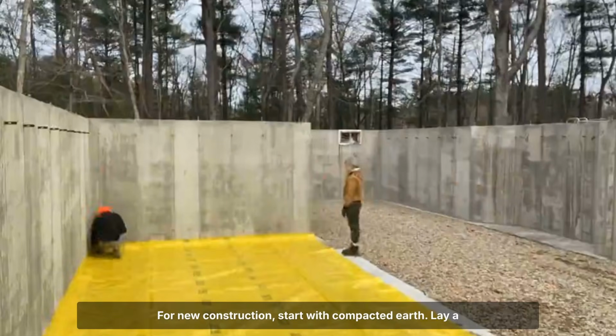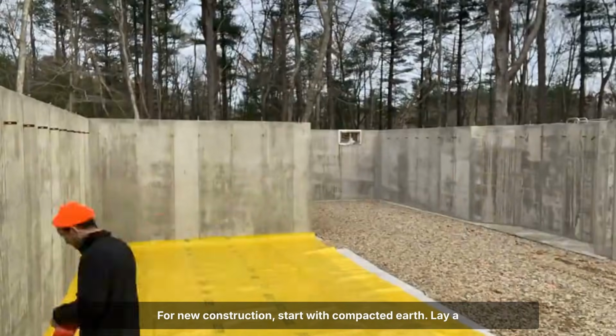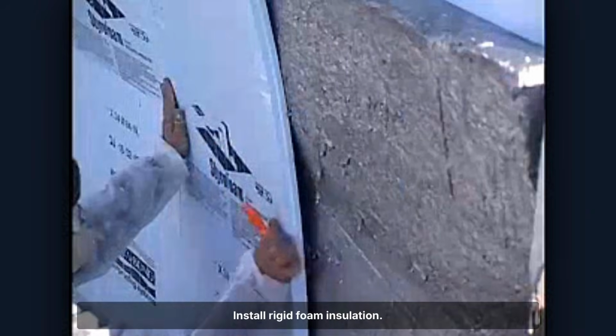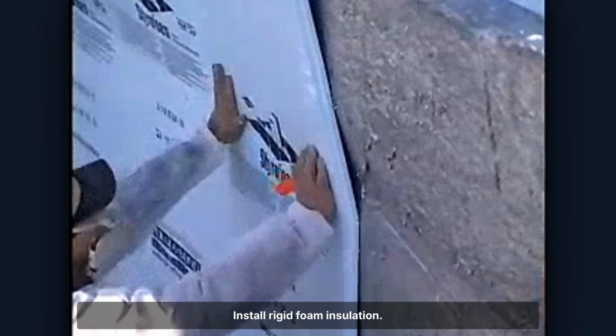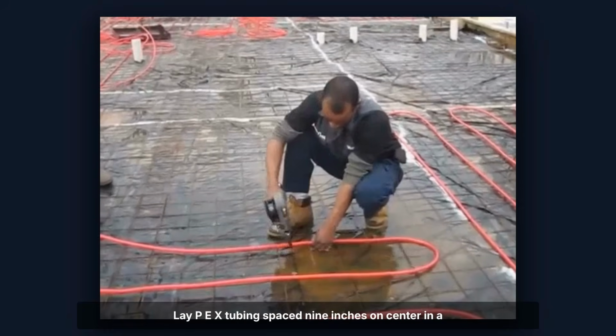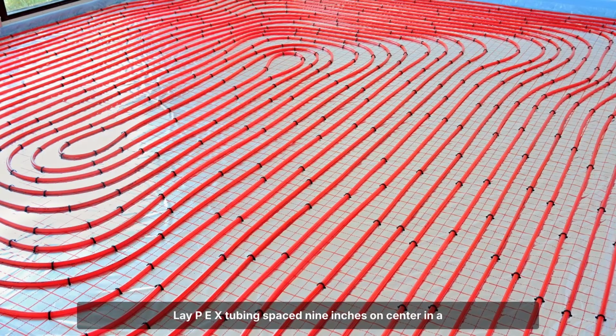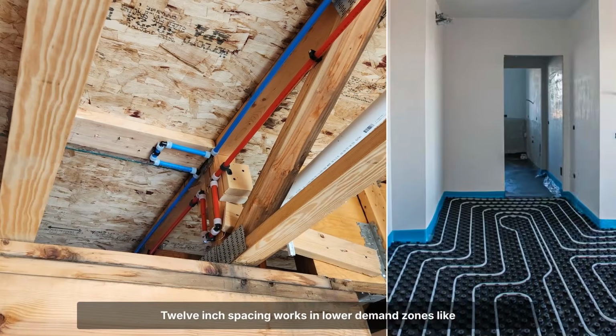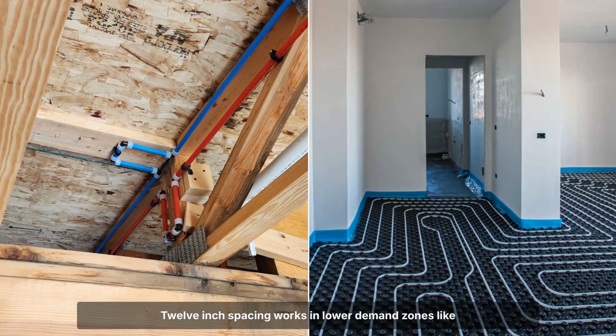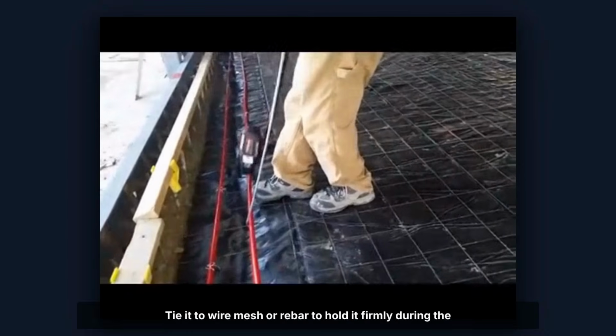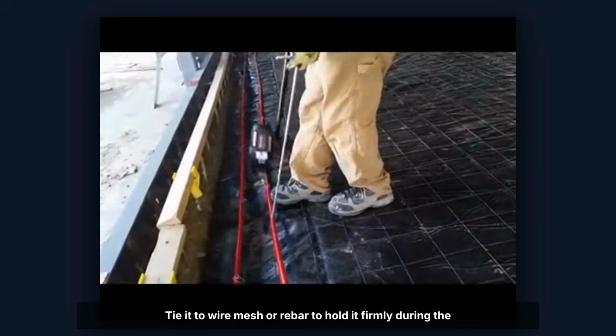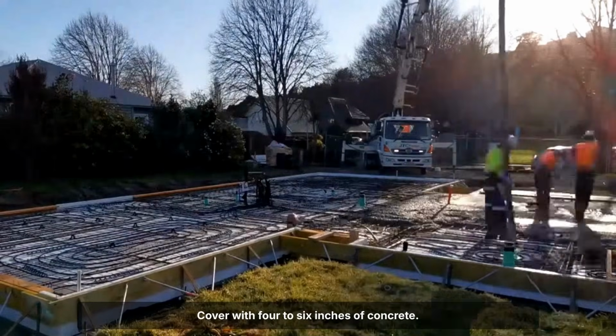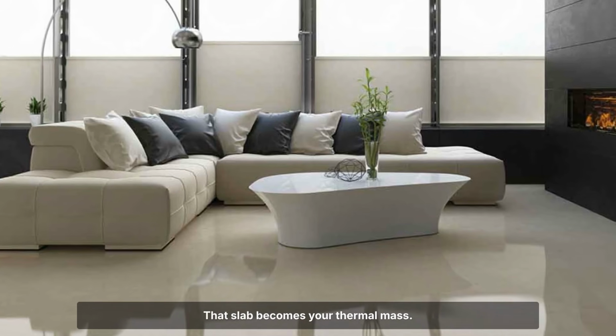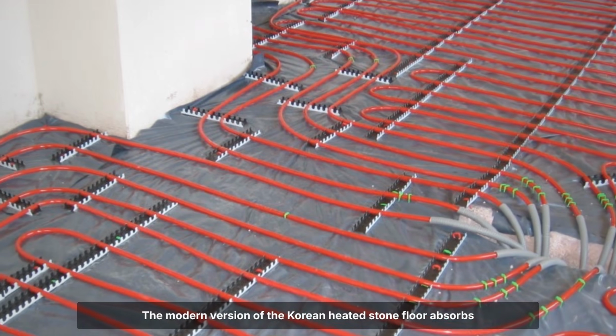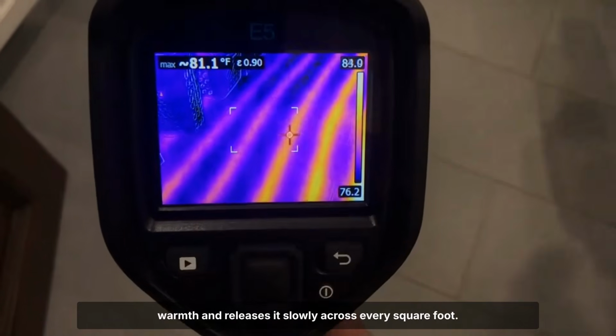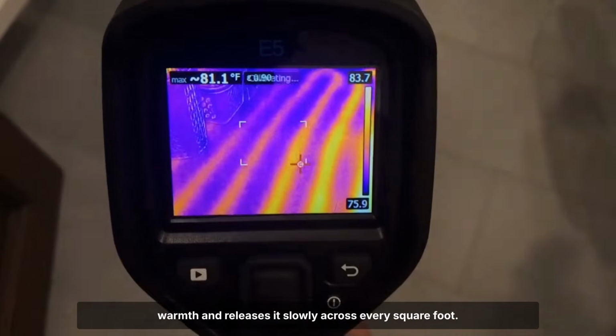For new construction, start with compacted earth. Lay a vapor barrier. Install rigid foam insulation. Lay PEX tubing spaced 9 inches on center in a serpentine loop. 12-inch spacing works in lower demand zones like hallways. Tie it to wire mesh or rebar to hold it firmly during the pour. Cover with 4 to 6 inches of concrete. That slab becomes your thermal mass. The modern version of the Korean heated stone floor absorbs warmth and releases it slowly across every square foot.